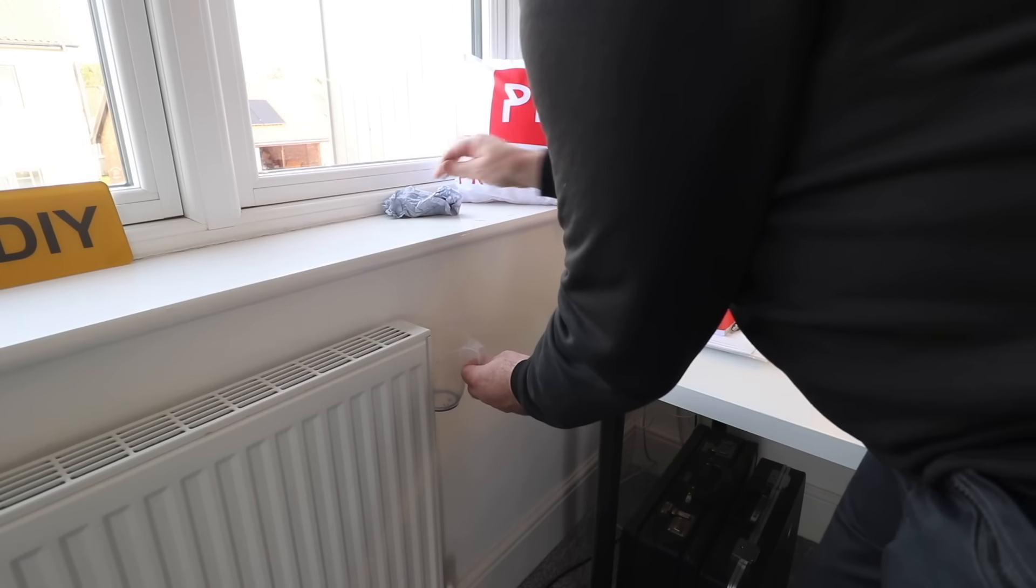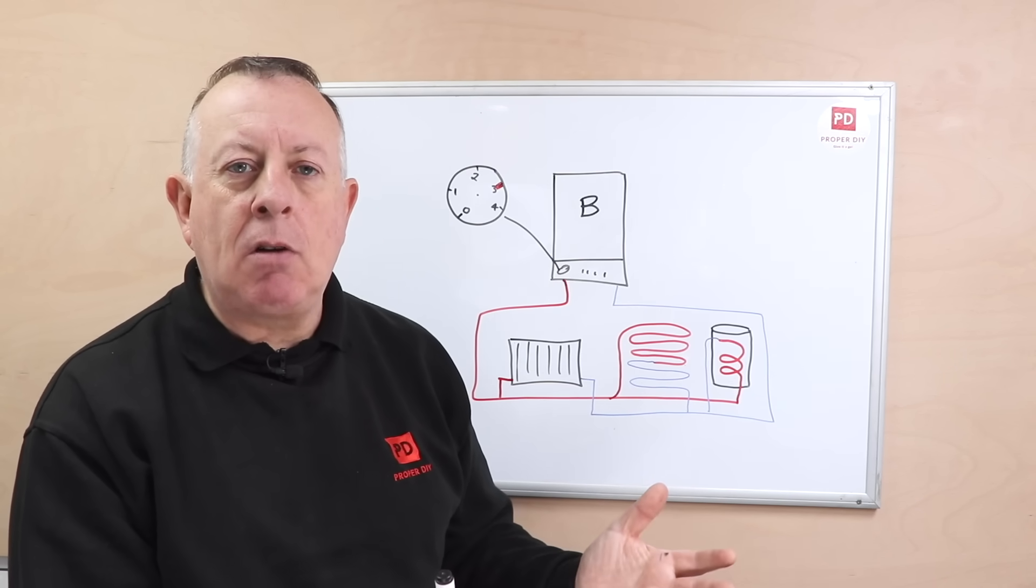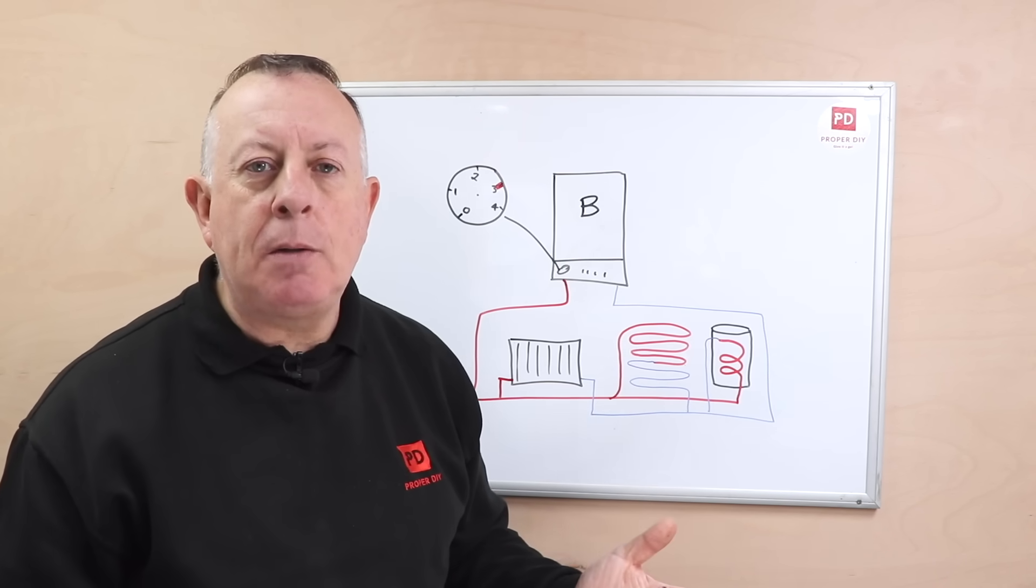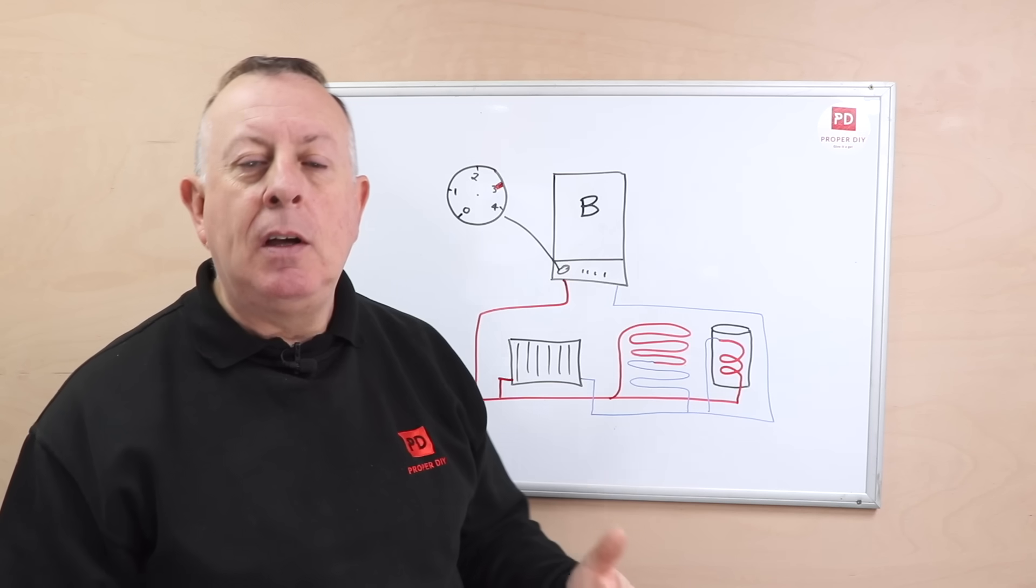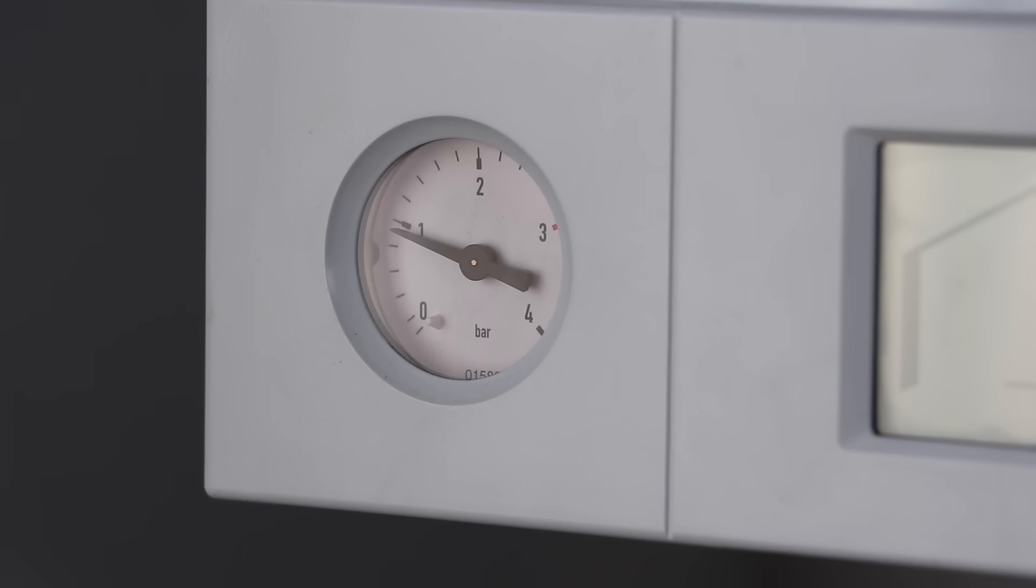Essentially removing that air and maybe a little bit of water from each radiator is enough to lower the pressure in this whole system, which is where we then need to go and top it up and make sure we're back to maybe one or one and a half bar. But that's obviously intentional.